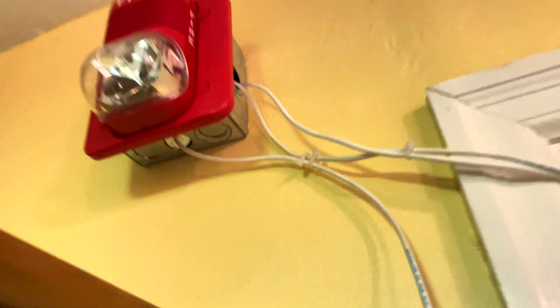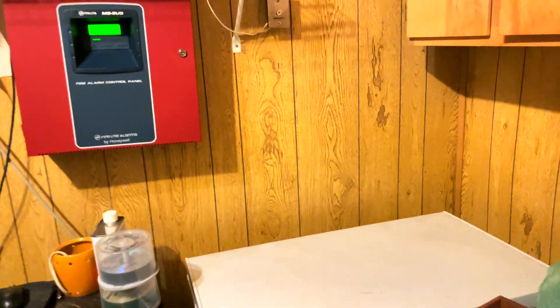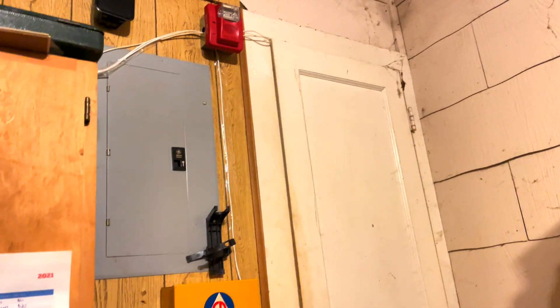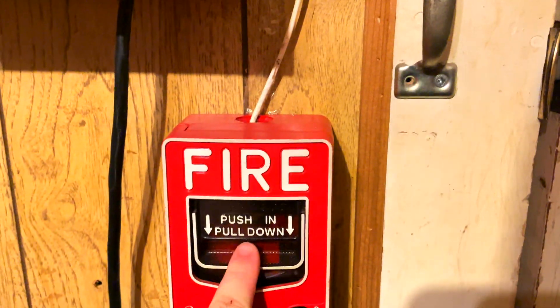It is a fixed 1575 strobe, as you can see. We'll go ahead and start the system test. The panel is set for System Sensor sync, and both of these alarms are wired for two-wire operation, which means I can use the selective silence feature on the MS-5UD. Without further ado, let's get this started — three, two, one.